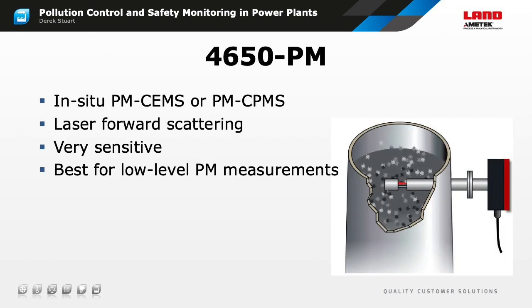The 4650 PM dust monitor uses a laser forward scattering measurement. The laser and electronics are mounted on a probe, part of which penetrates the stack. Near the end of the probe, the laser shines into an interaction region where the light is scattered by any particles which may be present. The scattered light is then collected and measured.